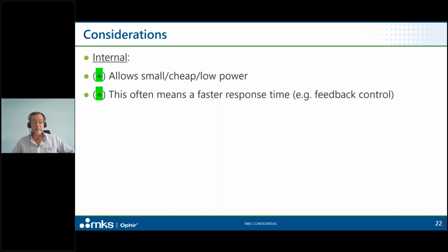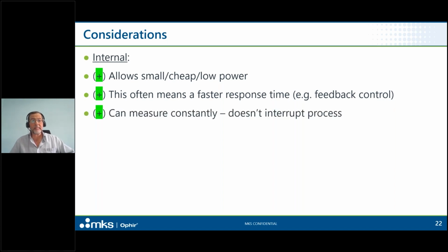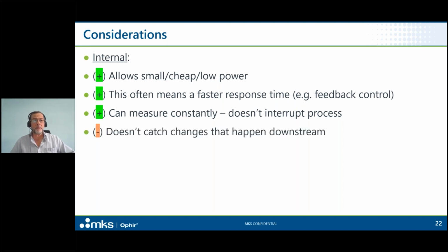Because I'm only off to the side taking a little bit of the beam, I'm not interrupting it, so I can have the process keep on working while I'm doing my measurements. Sometimes, not always, but sometimes that's an important consideration. The main downside is that I'm only checking the beam near the laser. I'm not going to catch unwanted changes that are happening farther downstream, such as one component in the delivery optics falling out of alignment, messing up my beam profile.